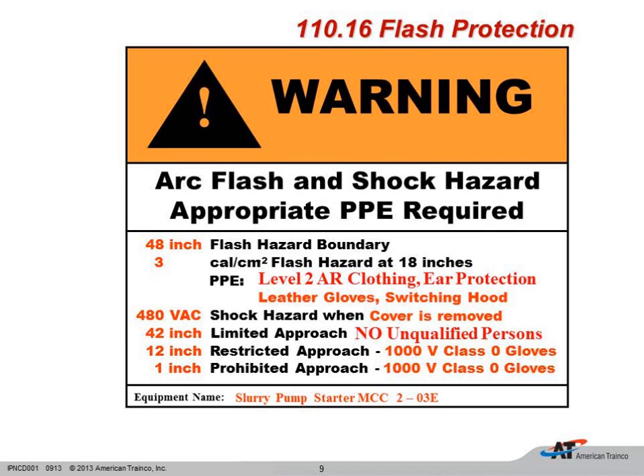So here we can see the label, and this label is actually addressing two NFPA documents, NFPA 70, the National Electrical Code. The top of the label, the warning, arc flash and shock hazard, appropriate PPE required, is what 110.16 requires at the time of installation, because the National Electrical Code, of course, is an installation guide. To get our installation approved by the authority having jurisdiction, we would definitely need the top part of this label.